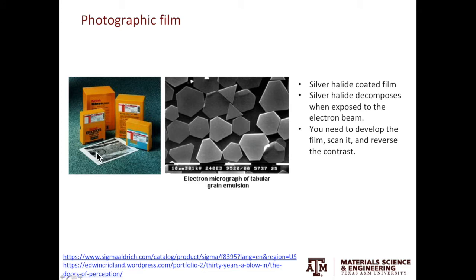The second way to record images is to use photographic film, and this is the end product you get — a physical photograph. The photographic films are coated with silver halide. When exposed to the electron beam, the silver halide will decompose. More electrons hitting a certain region means more silver in that region, and darker it will appear on the photograph. After acquiring the images, you need to remove those photo plates from the TEM, develop the film, scan everything, and reverse the contrast.